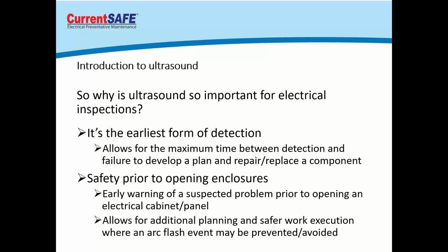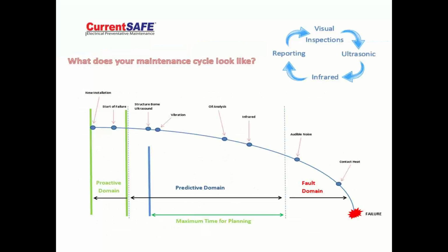Maybe go to the customer and tell them it's time to perform lockout on this and shut it down during scheduled maintenance because of what we hear behind the cover. Then they can record that sound, listen with the customer, do signal analysis, and put it on a screen for them to see, breaking down what they've recorded. It's a great tool, especially for our technicians to stay safe before opening panels and electrical distribution covers to perform infrared and other visual inspections.